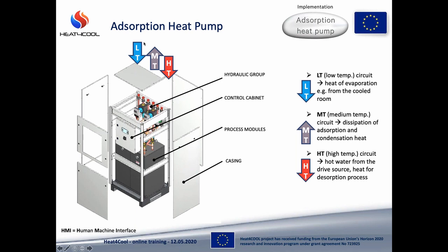Here at the top, you can see the connections of the three circuits mentioned above. The LT has to be connected to the cold distribution circuits, for example, fan coils. The HT has to be connected with a source of heat, for example, solar collectors. And MT is the heat dissipation circuit. This one may be connected with a dry cooler, wet cooling tower, swimming pool, underground heat exchangers, basically anything where you can dissipate the heat at proper temperature levels.